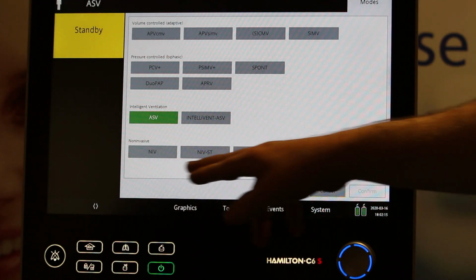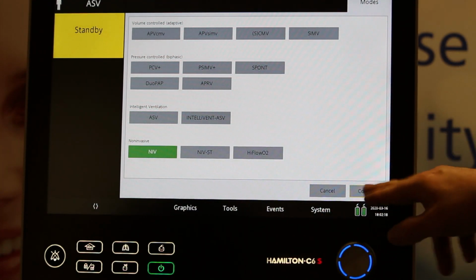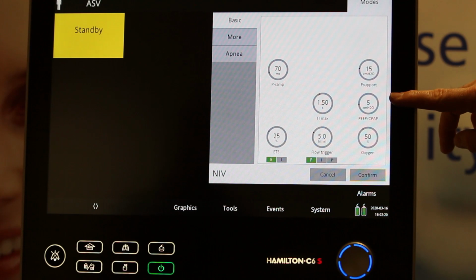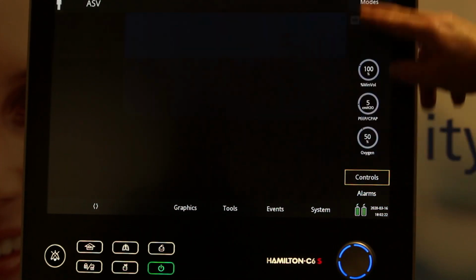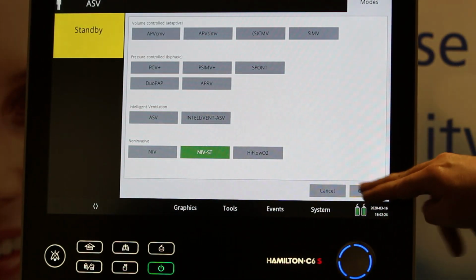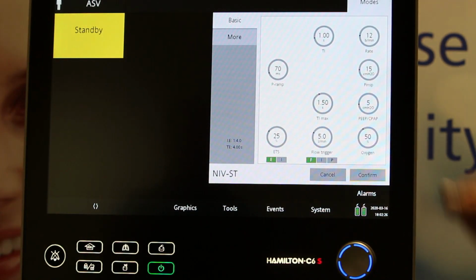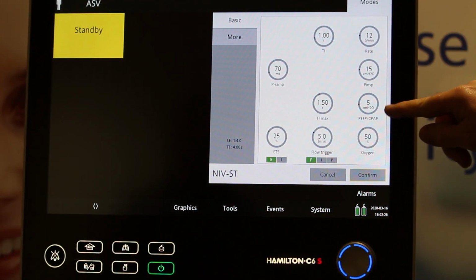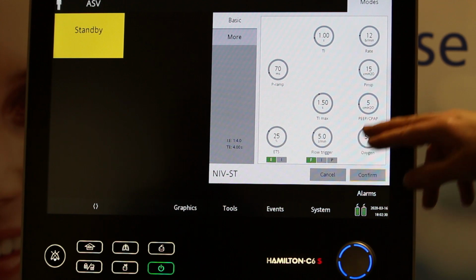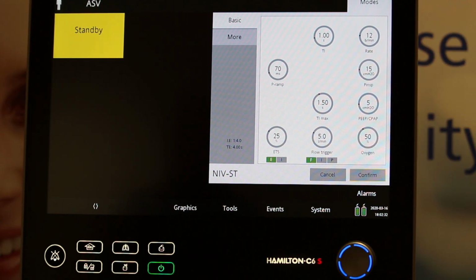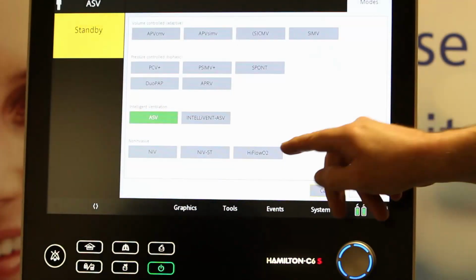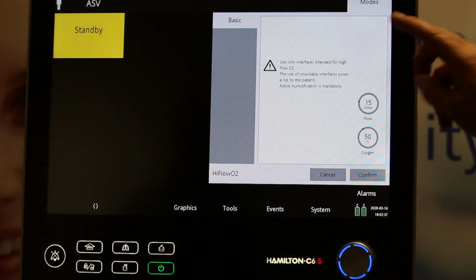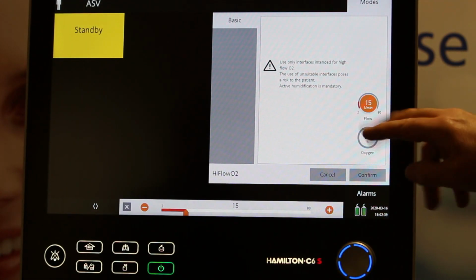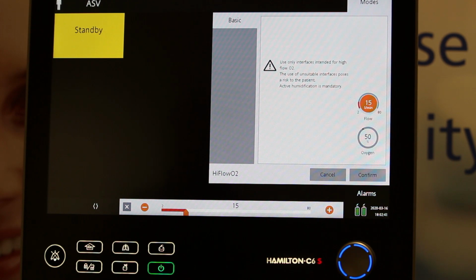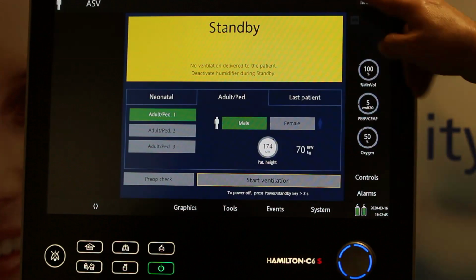And then underneath them you can see we've got our non-invasive mode. So we've got NIV, which is your non-invasive, so you're setting your pressure support on your PEEP. Then all breaths are triggered. And then we've got NIV ST. ST stands for spontaneous and timed. So I'm setting my pressure support on my PEEP, but I also have an I time and a rate. So that is my non-invasive BiPAP. And then we have our high flow, where you're just setting your flow and your FiO2. Hamilton ventilators will do a maximum flow of 80 litres per minute for high flow.